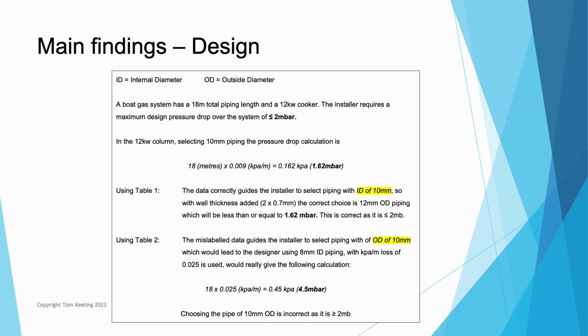So looking here at this example, and you can pause and read through this to please yourself there, but the essence is there in the bold. We're looking for a design drop over a system of equal to or less than 2 millibars. Using the table on the left, the correct one gives us 1.62 for our example. Using the incorrect chart on the right hand side gives us 4.5. So from the start, the designer has built in a problem to that gas system.